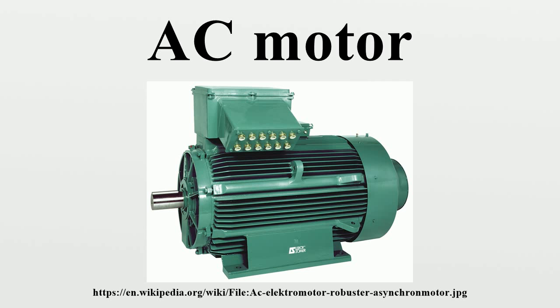Induction motor. Slip. If the rotor of a squirrel cage motor were to run at the true synchronous speed, the flux in the rotor at any given place on the rotor would not change, and no current would be created in the squirrel cage. For this reason, ordinary squirrel cage motors run at some tens of RPM slower than synchronous speed. Because the rotating field effectively rotates faster than the rotor, it could be said to slip past the surface of the rotor. The difference between synchronous speed and actual speed is called slip, and loading the motor increases the amount of slip as the motor slows down slightly.